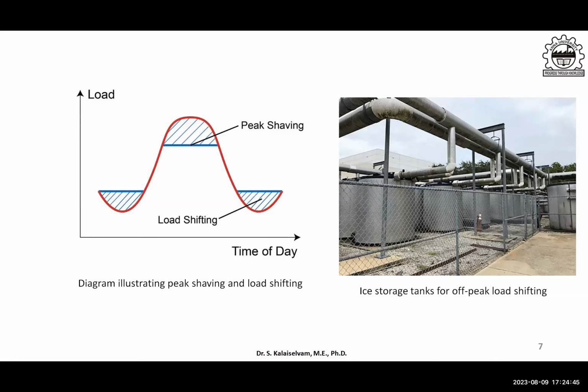Normally in a conventional HVAC design, we used to design an air conditioning or cold thermal storage system for peak load. So here we used to design a HVAC or cold storage system for this peak load. If you include a TESS, instead of designing the system for this peak load, you can design it for a lower peak load. Hence, any load beyond that will be taken care of by the energy stored in the storage tank, the TESS storage tank.